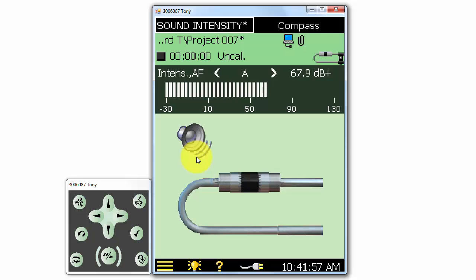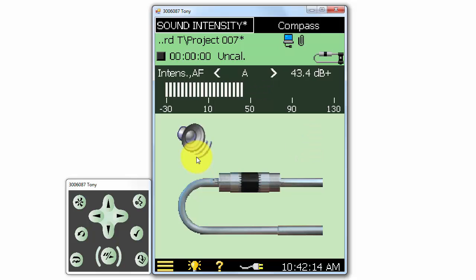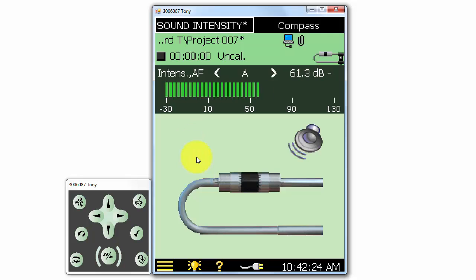For example, if we are scanning the probe horizontally across a source, we can slowly move the probe across, and as the probe passes the sound source, we will see the sound direction change to indicate the location of the leak. As the probe moves across the sound source, the speaker icon will move to indicate whether the sound source is behind or in front of the probe. If we move the probe parallel to the surface horizontally and vertically, we can identify a sound leak at a point in the XY plane.